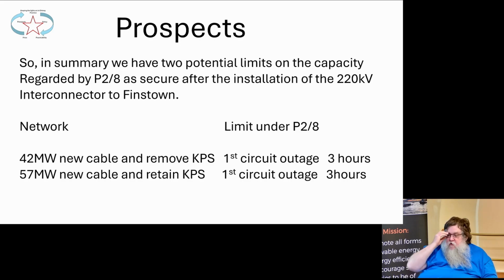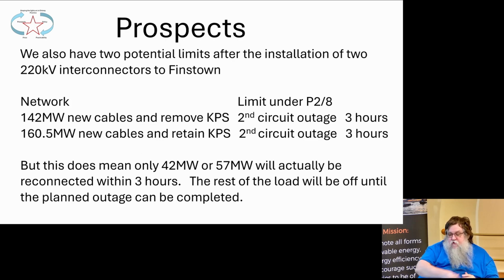With two potential limits on the capacity regarded by P2/8 as secure after the installation of a first 220 kV interconnector to Finstown, that's 42 or 57 megawatts, one without the power station and one with, and the limit is the first circuit outage. It's got to be restored within 3 hours. And if we put two 220 kV circuits in, the limits are 142 and 160.5, and those limits are not first circuit outages, they're second circuit outage limits, which have to be restored within 3 hours. But even if you go to that situation, it means only 42 or 57 megawatts will actually be reconnected within 3 hours. The rest of the load will be off until the planned outage can be completed, if it is a planned outage.